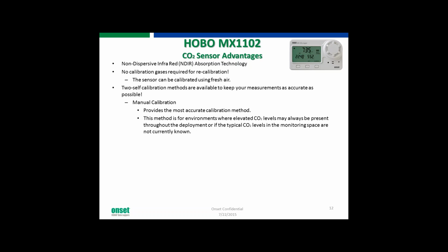I can tell you that in a building such as ours at Onset, there are not people in there 24/7, so at night the CO2 levels, it's fairly well ventilated too, so the CO2 levels do go down to the outdoor range at night when no one's there, so the automatic calibration mode would work fine in a space like that. But manual calibration gives you a better handle on keeping that calibrated, again, in spaces where you don't quite know what's going on.